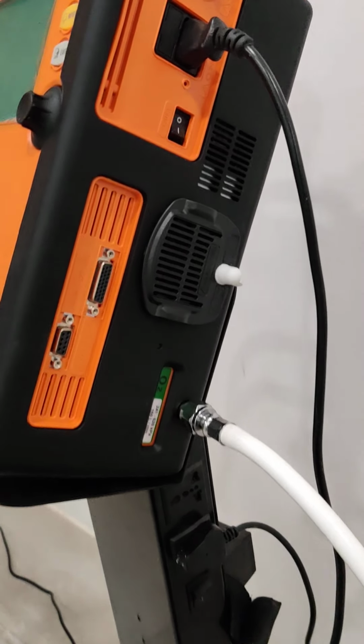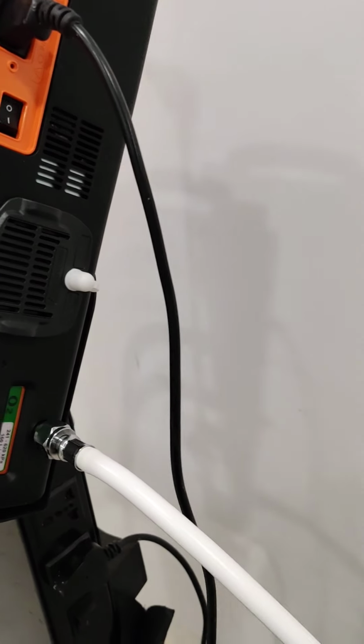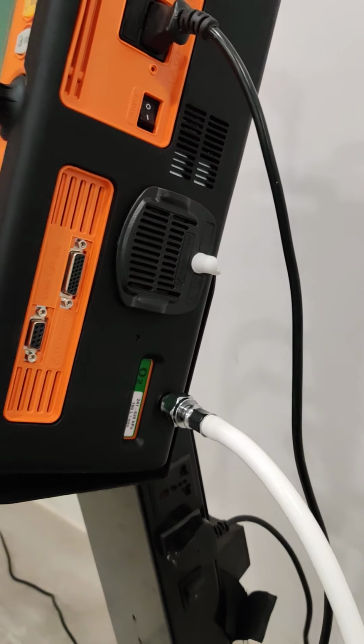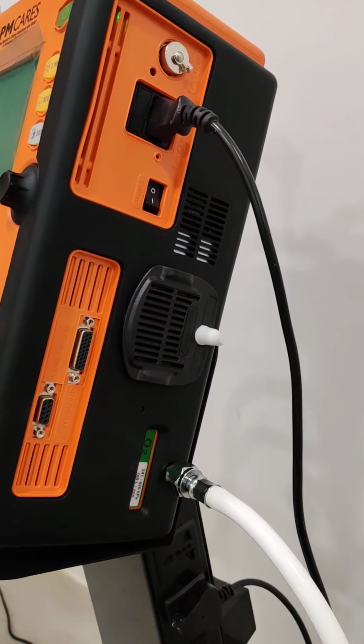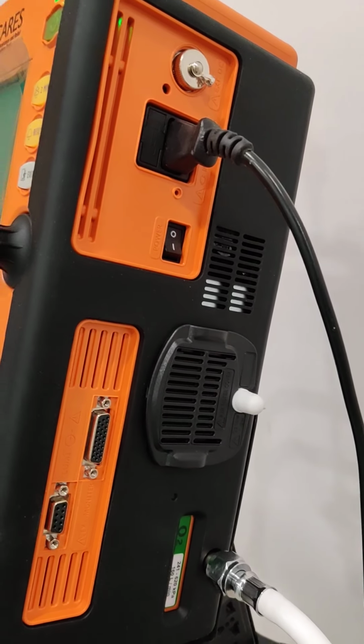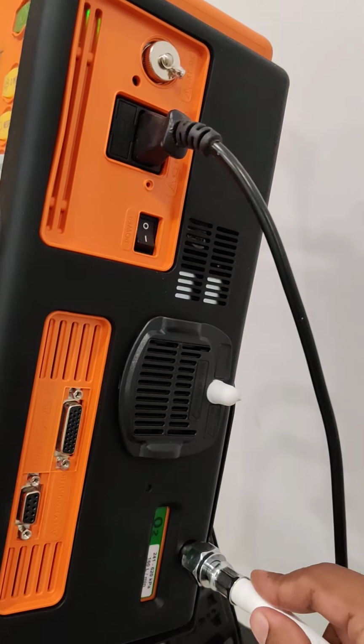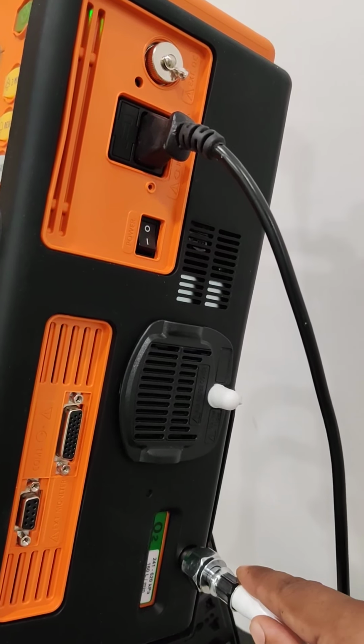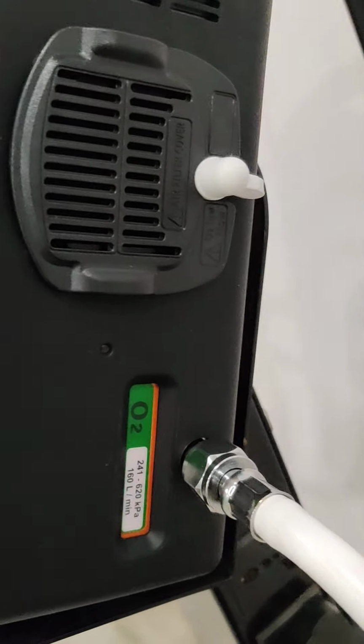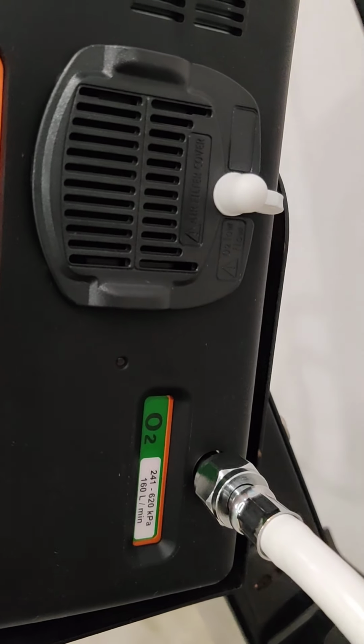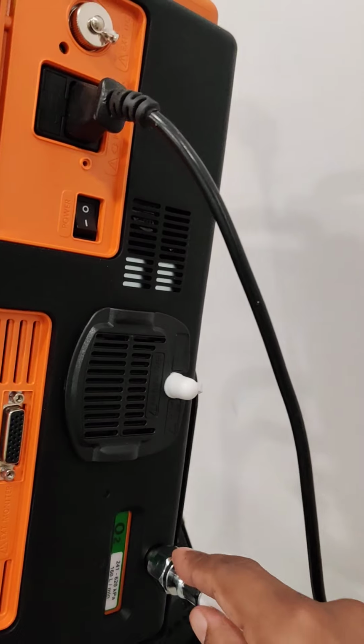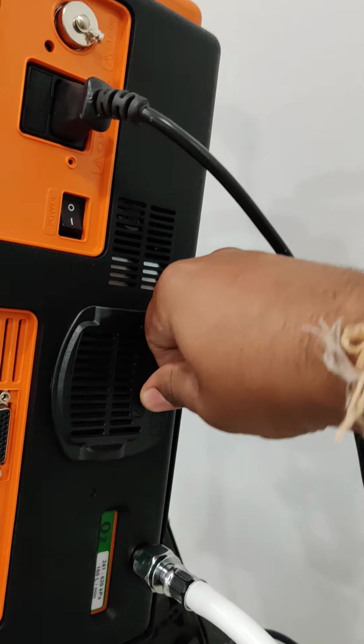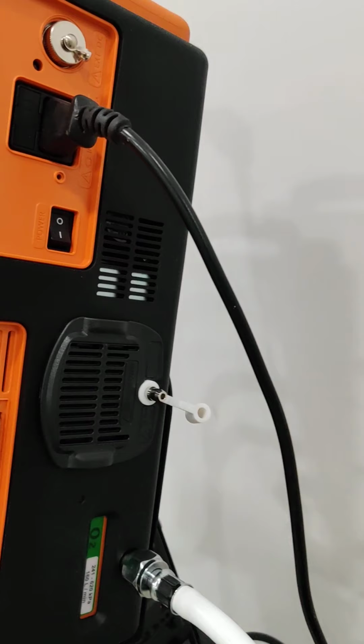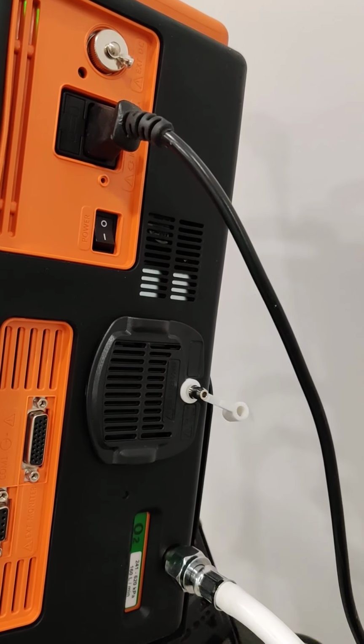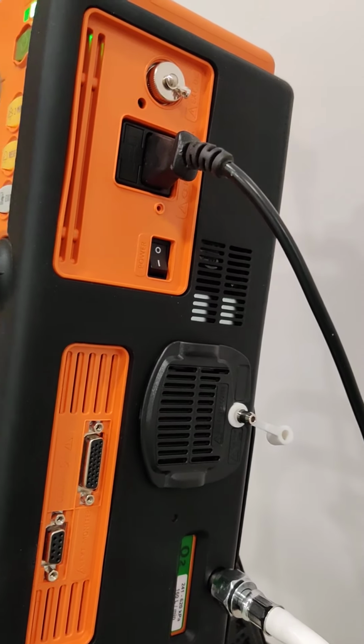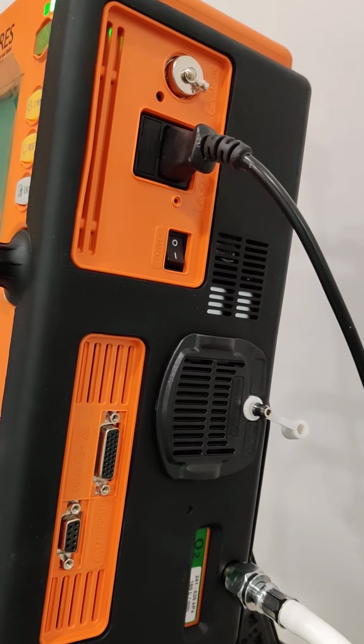So one end of the tubing will be connected onto the ventilator, and the other end of the tubing will be connected to the central supply or to the cylinder through a MOX regulator. So for this ventilator, the oxygen enrichment can be done in two ways. One is with the high pressure, like from the cylinder or the pipeline, but the input pressure should be between 241 to 620 kilopascals. And the other way of enriching the oxygen is by connecting the auxiliary flow meters on this port, and whatever flow you set on the oxygen concentrator or the auxiliary flow meter, that much oxygen enrichment will be done and given to the patient.